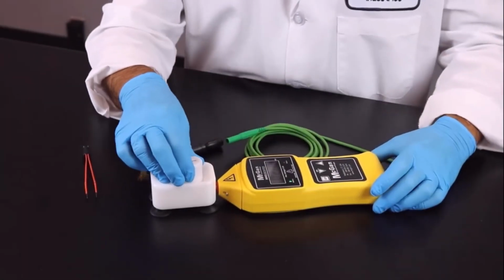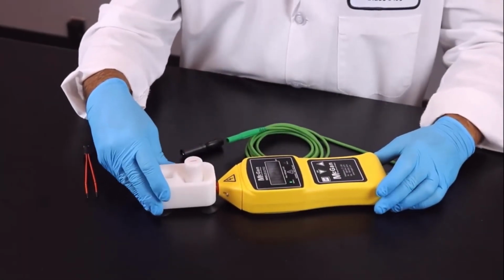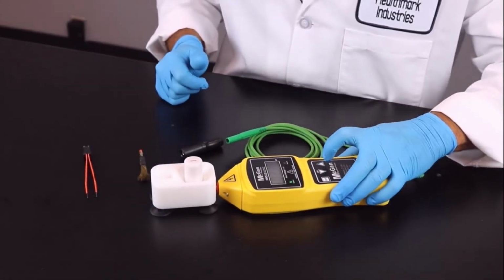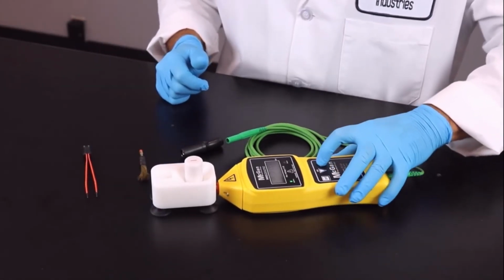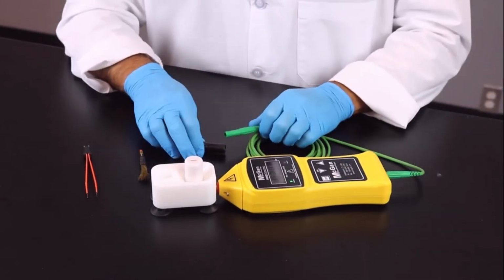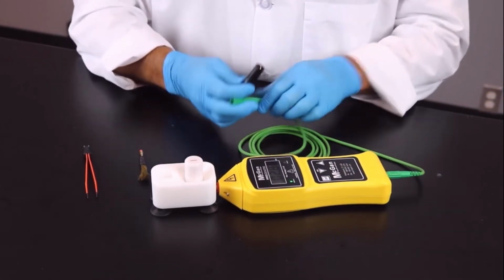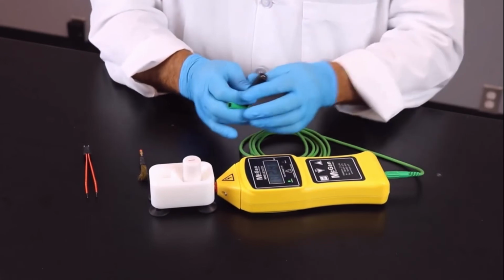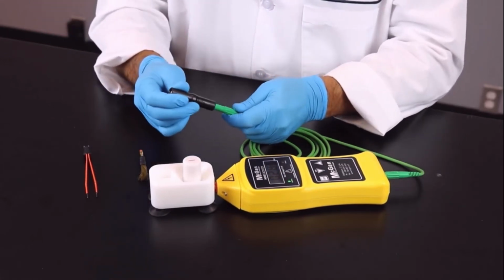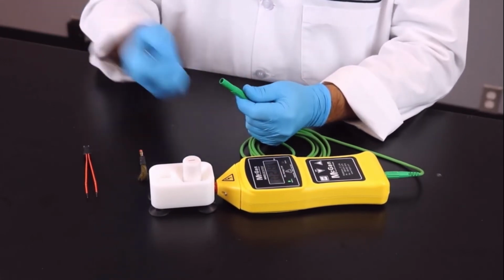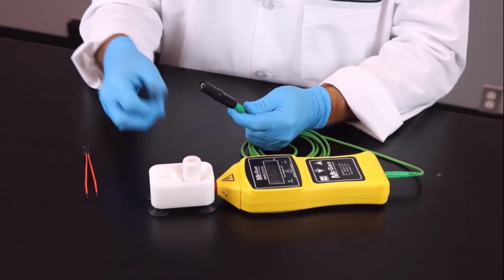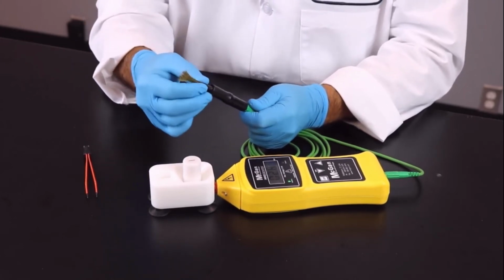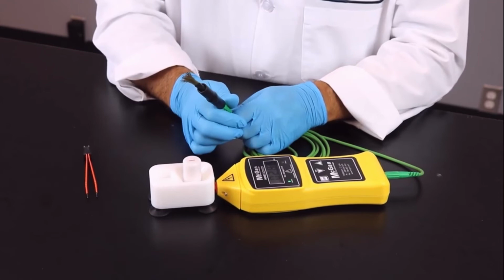After you connect the bipolar fixture to the saddle block and the saddle block into the unit, you want to set the voltage at 2.8. Once you got that in place, you want to make sure you get the grounding wire hooked up to the bottom of the base of the unit. The black connector would go after you take off the alligator clip. Place that on there and place your wire electrode onto here like so.